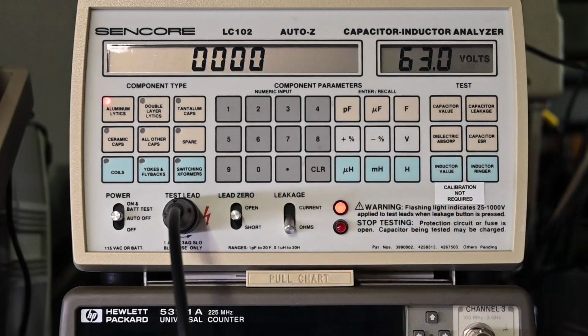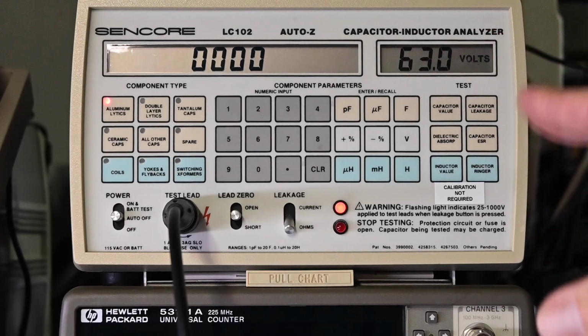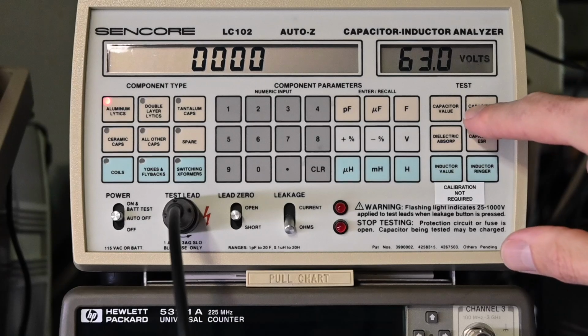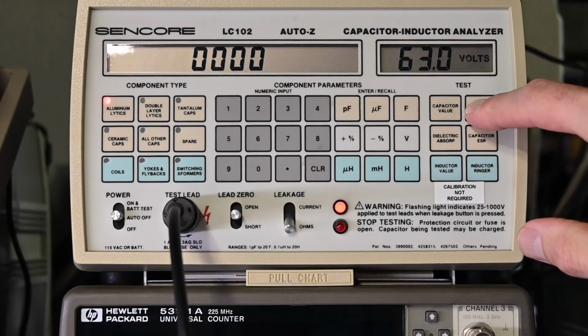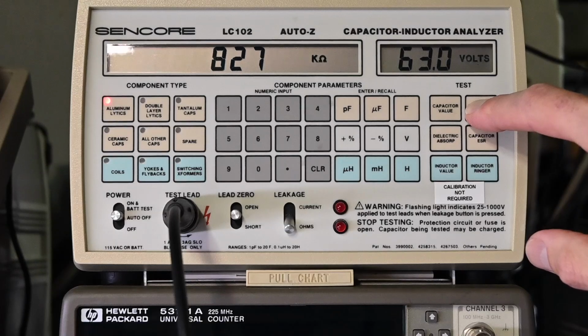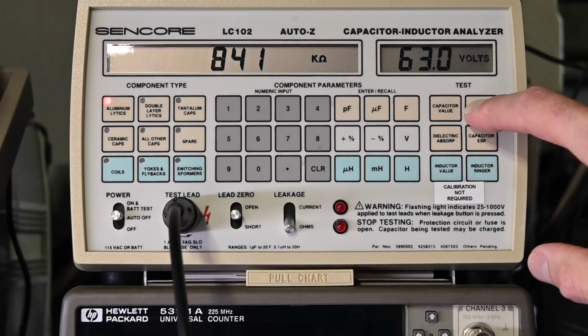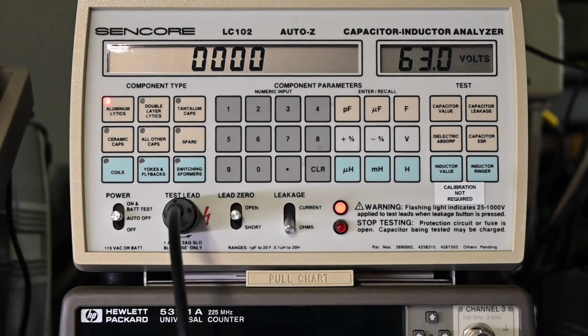Now, if I go to ohms right here, it'll just basically convert that current reading over to resistance because it knows the voltage, and when you know voltage and current, you can compute resistance. So if we do this again, it'll just tell us what the resistance of that capacitor is. And as I mentioned, the capacitor is basically turning into a resistor when it becomes leaky. And you can see right there, so 828 k ohms, 832. So just imagine putting an 800 and about 850 k ohm resistor in that circuit. That's going to have an effect. It's a high value, but nonetheless, it can't be ignored. So you can clearly see the capacitor has a problem. So definitely faulty, needs to be replaced.